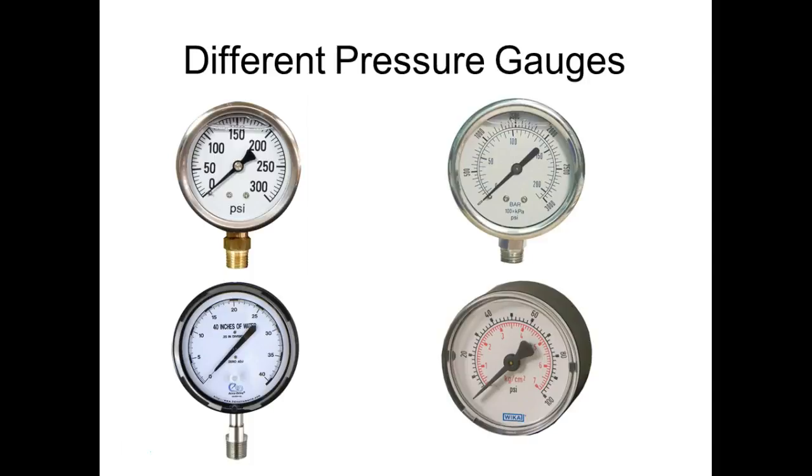Most of our meters, you're going to see a lot of them have multiple scales on them. The one on the top left, by the way, did y'all see the fluid in there? When I first got involved with this, I saw that and I called up the company and said, there's fluid in my meter. He says, that's a gel. It's in there to dampen the meter, so the meter doesn't vary, especially on compressors and pumps.